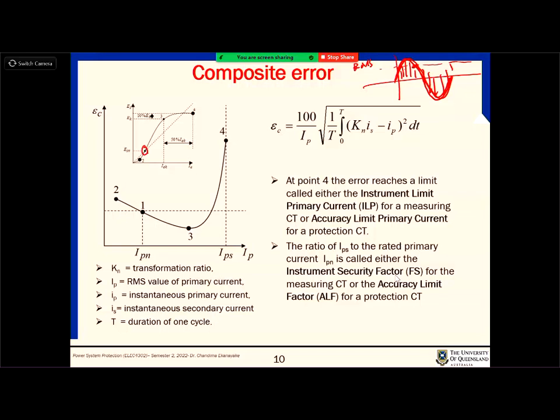So what you need to understand is that when we change the primary current, the magnitude of error changes in such a way that at 4, the error is reaching a limit which you can't bear more than that. I don't want to use this transformer beyond this. This is a limit for the error, right?